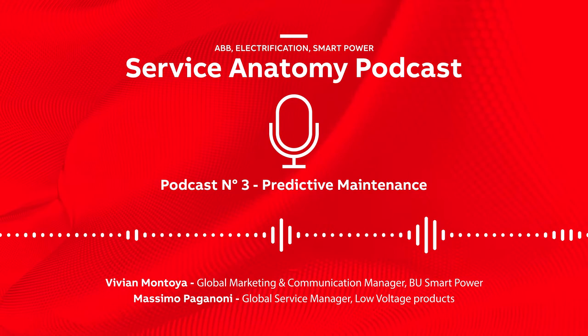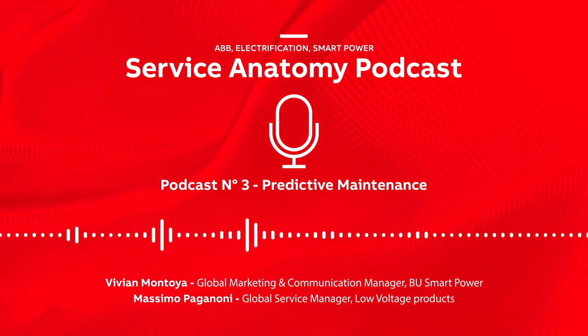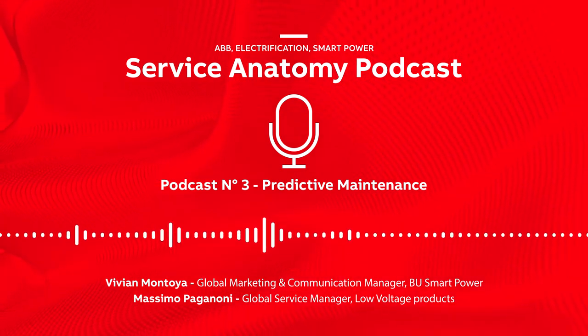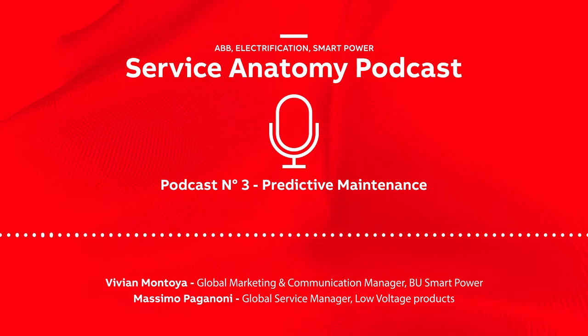Very interesting. I want to know how the predictive maintenance works, because for me it's not so clear. You know, Vivian, different key data, such as the number of mechanical operations, the nominal current, the interrupted overloads and short circuit, and the environmental conditions, such as humidity, temperature, vibration, and corrosion, are all collected directly from the circuit breaker. Then, the ABB predictive maintenance algorithm defines accurate mechanical and electrical aging trends, and the result is that the breaker health condition is represented by colors, where the failure risk increases if the aging curve passes from green to yellow, to orange, and to red.